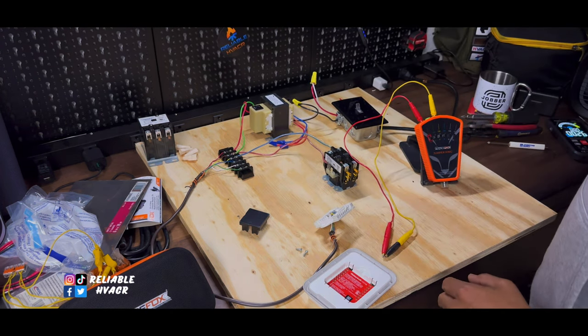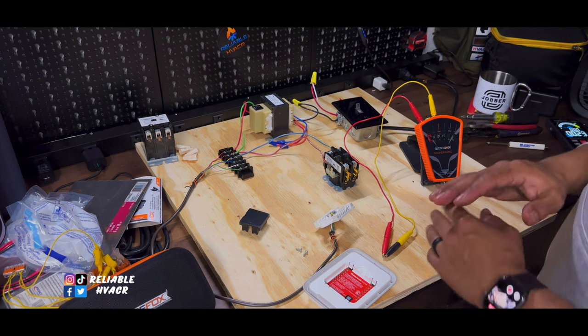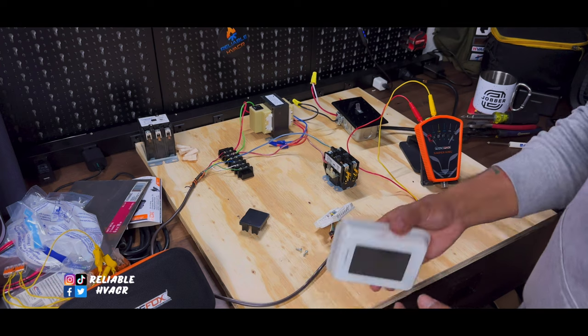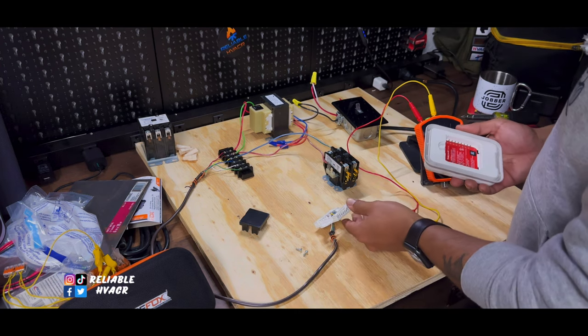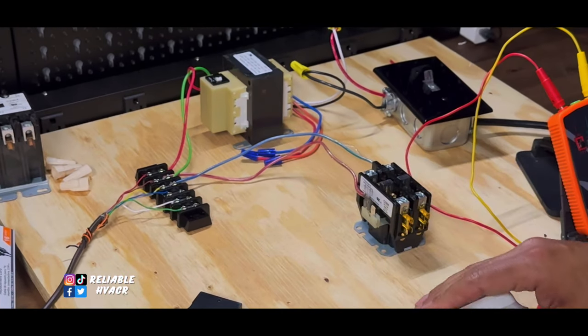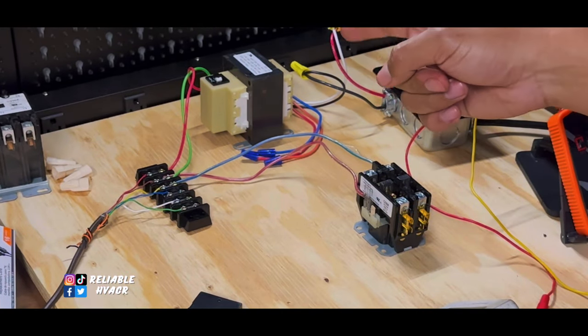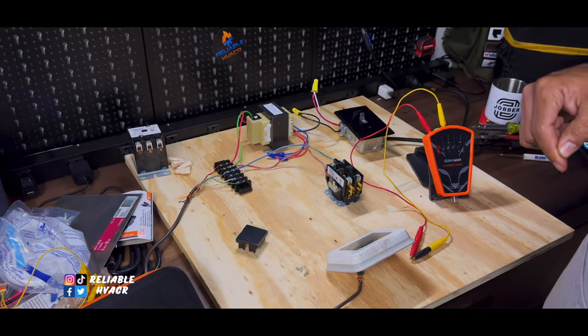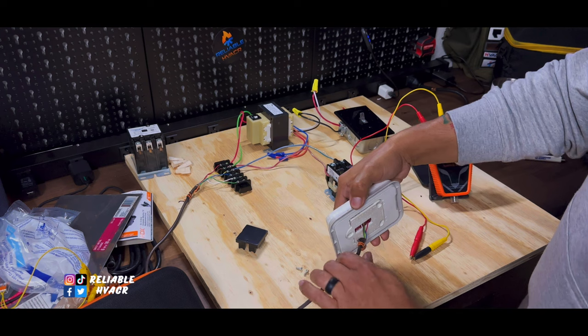So, then, nothing is energized, right? No contactors are coming on. So, then when I went to go put this, I mean, I didn't know what was going on right away. I'm going to plug this in, transformer pops. That breaker was popping because of this thermostat.